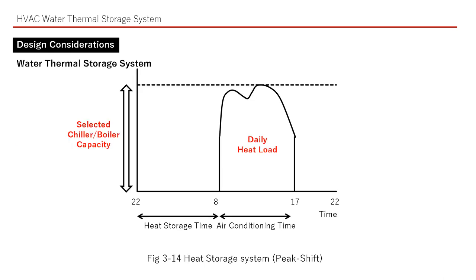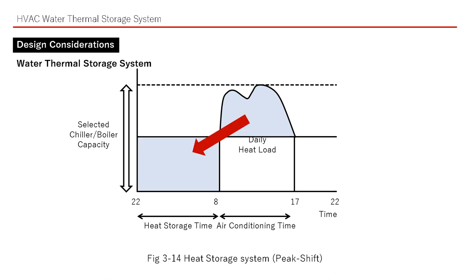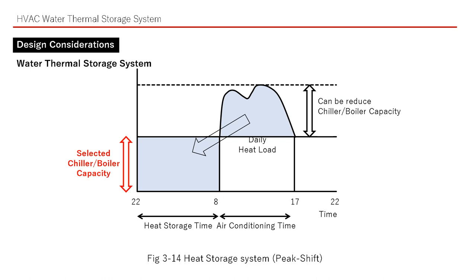Let's reconfirm the concept of the thermal storage tank using the graph. Air conditioning time is 8 to 17 o'clock, and there is a curve for daily heat load. Chiller or boiler capacity is selected based on the peak load, making it a large capacity equipment. By dividing the daily heat load and shifting it to night time, we can reduce the peak load and select smaller capacity equipment.